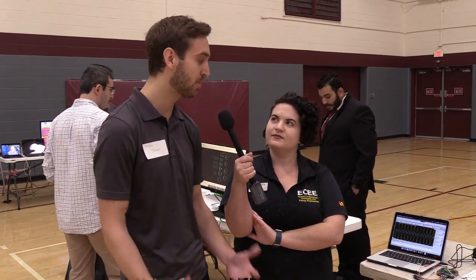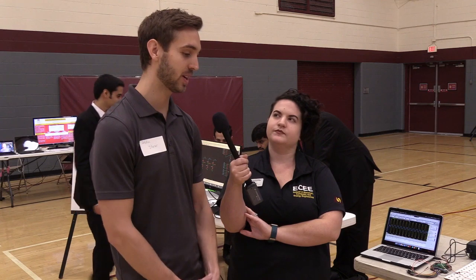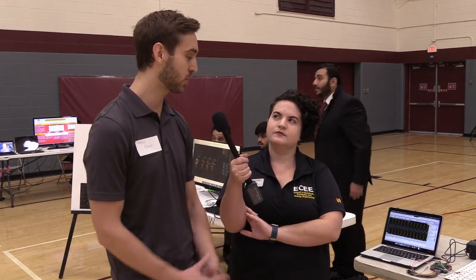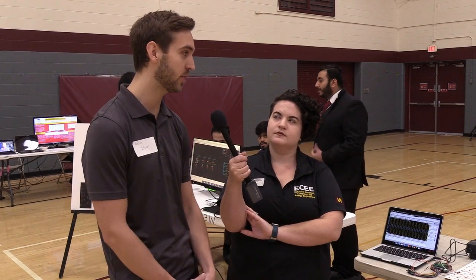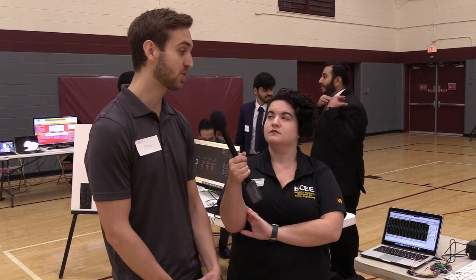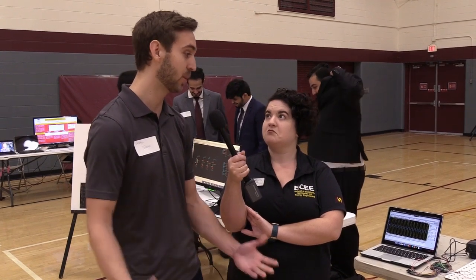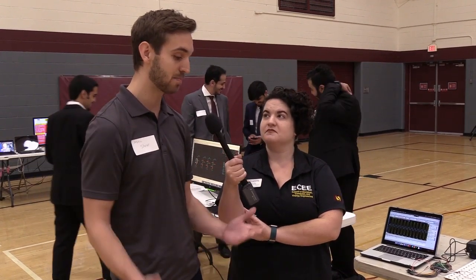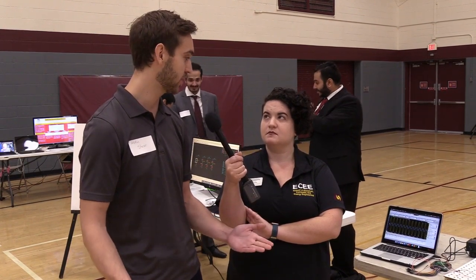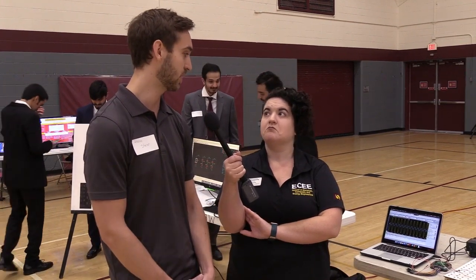So we designed a current differential for a single-phase transformer. Basically, it's a protection device that protects critical components in power systems. High power systems need something to protect from faults or shorts to ground. These kinds of faults can cause fires, hurt people, and damage equipment. We're talking millions of dollars when we're talking about components this large. These types of devices can monitor the waveforms on these lines, sense a difference in them, and then send a signal to a device which will open the circuit, protecting that component.